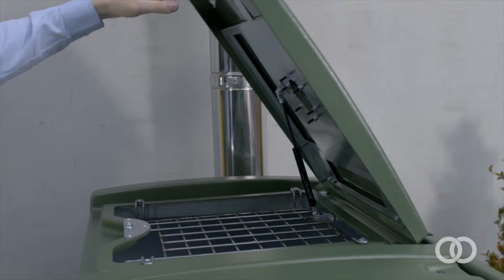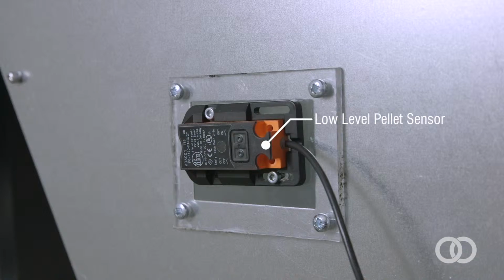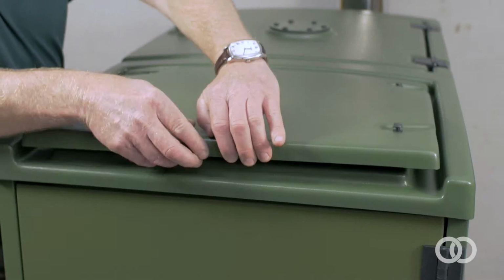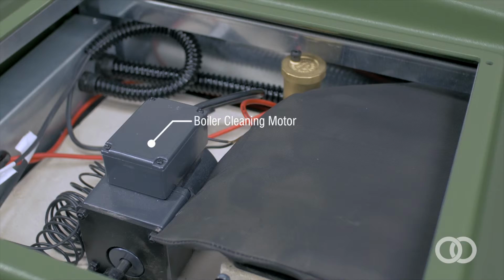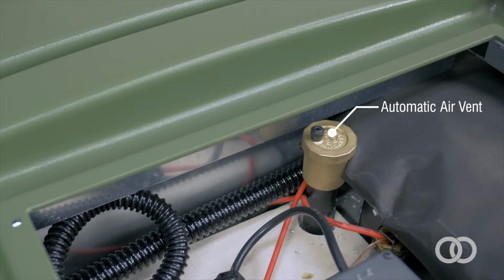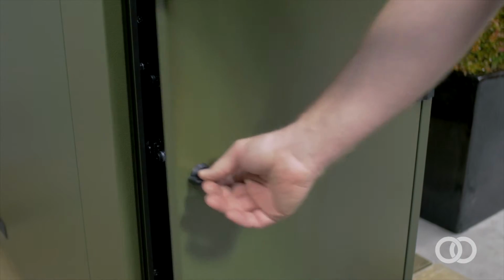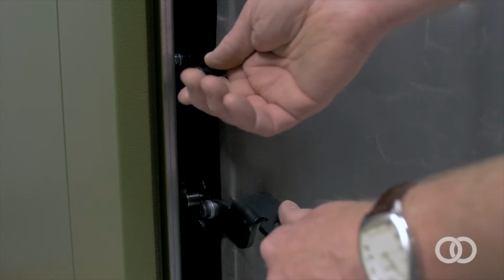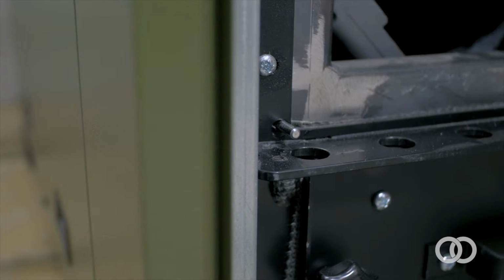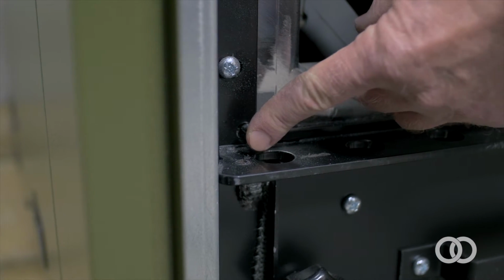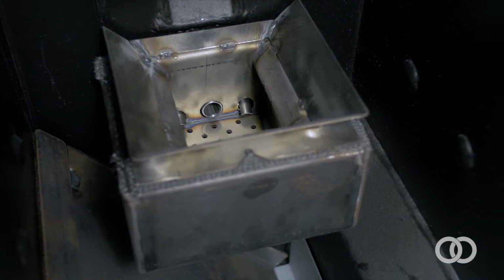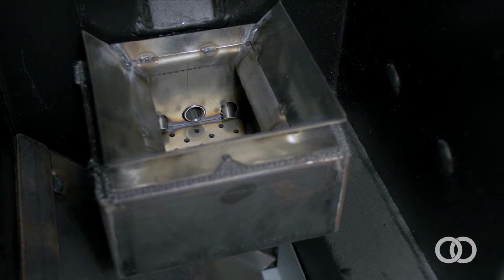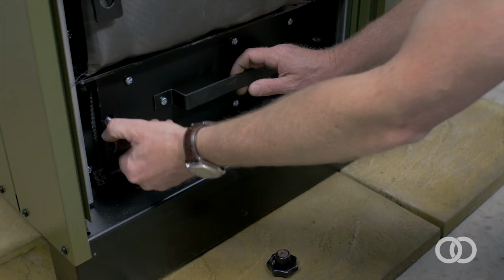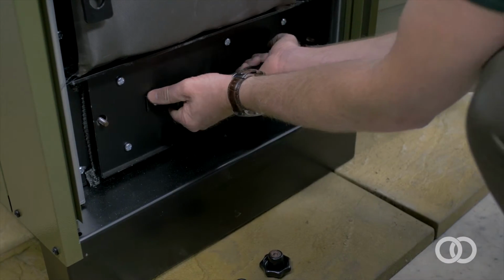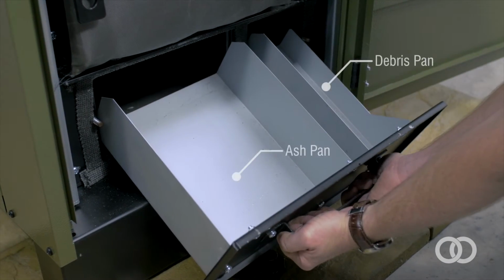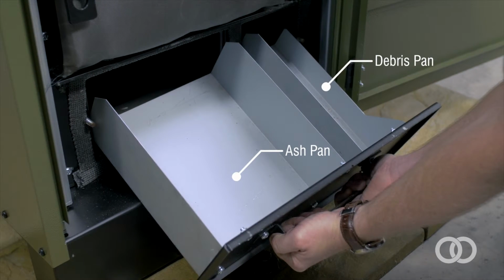Within the hopper you will find the low-level pellet sensor and the auger flight. On opening the lid over the boiler, one will find the boiler cleaning motor and the automatic air vent. On opening the front door of the boilers you will notice an additional safety catch that needs to be opened on the combustion chamber door. This is in addition to the existing electronic safety switch. You will notice the burner pot and grate which is manufactured from stainless steel. A generous ash pan is located at the bottom of the combustion chamber and a pan for collecting the debris after cleaning the heat exchanger.